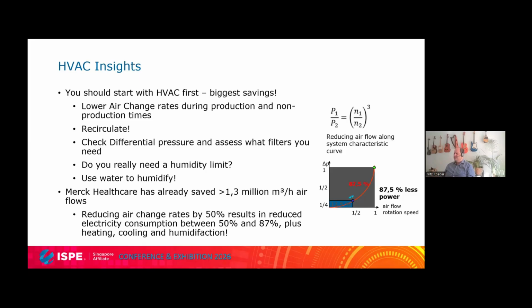Differential pressures bring a little less energy savings, but nevertheless, you can have a look at it. Filters: do you really need H14 HEPA filters that have even 1 log higher separation efficiency than the H13 filters? And to be honest, if you have, let me say, a non-sterile clean room, you could even achieve the clean room specification with an F9 filter. HEPA you would not basically even need, but then you have the cross-contamination topic. So here it is maybe still advisable to have these H13 filters, but check it out.